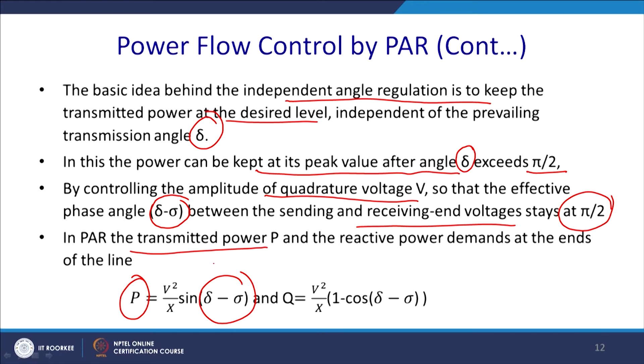So, you had P, that is V square by X sin delta, in this case it becomes delta minus sigma, and the reactive power also changes, V square by X into 1 minus cos of delta minus sigma. The phase angle regulator does not increase the transmittable power of the uncompensated line. Please understand that the angle does not increase the value of the P max, but it can shift the P max.